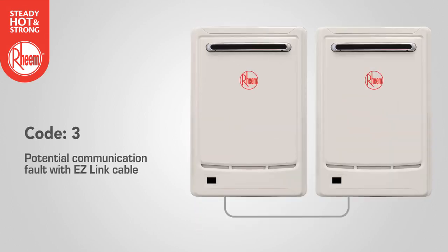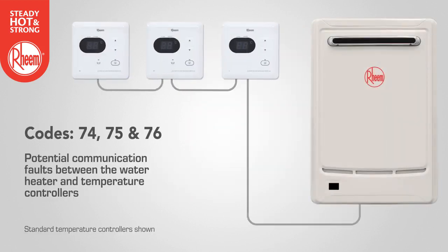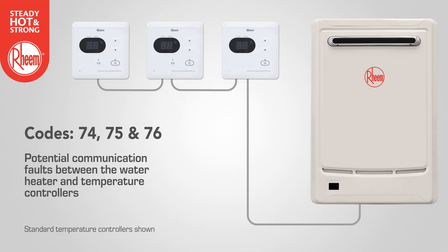Code 3 refers to a potential communication fault with the EZ Link cable between two water heaters — confirm the link cable is installed correctly. Codes 74, 75 and 76 refer to potential communication faults between the water heater and remote temperature controllers. Confirm the link cable is installed correctly. Where multiple controllers are installed, check that cables are correctly installed between controllers and the water heater. Note that a maximum of three controllers can be connected to a single water heater. Finally, check for compatibility where a new water heater may have been installed with an earlier model controller.